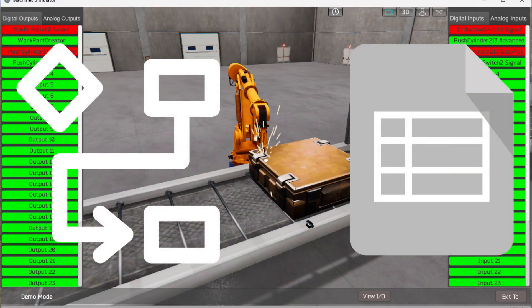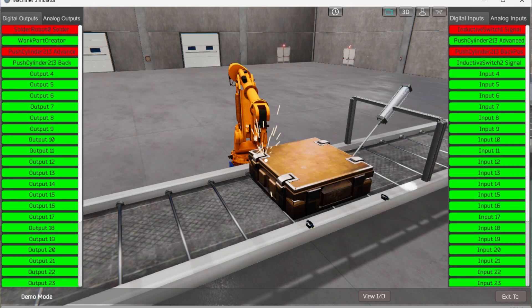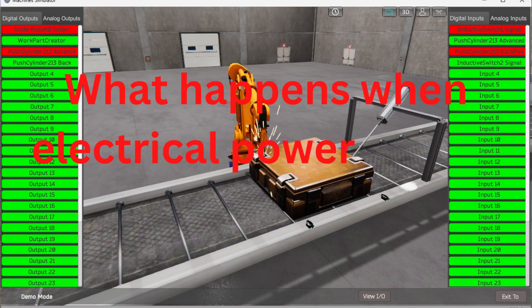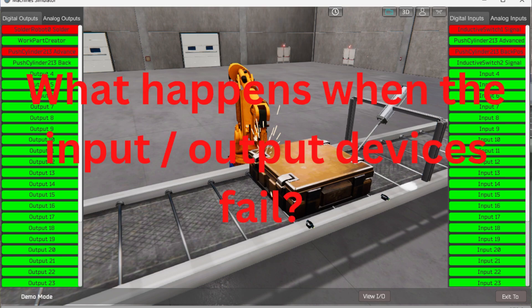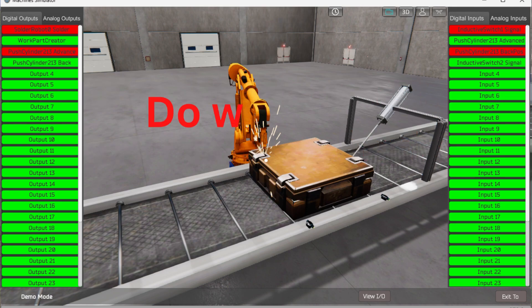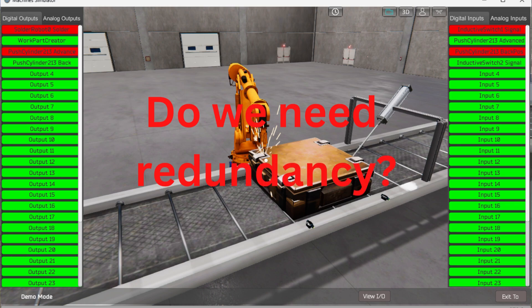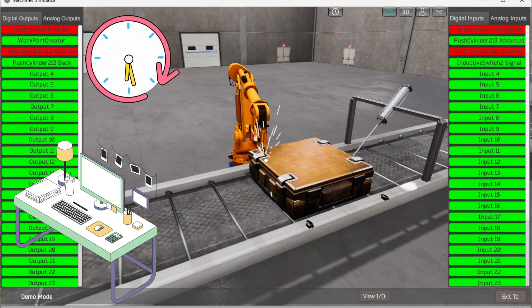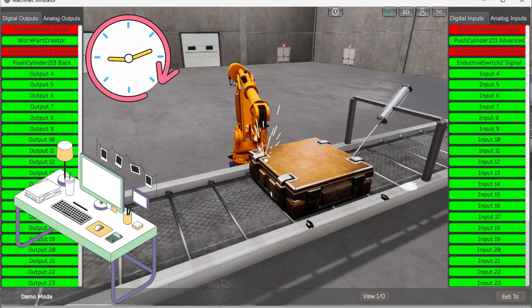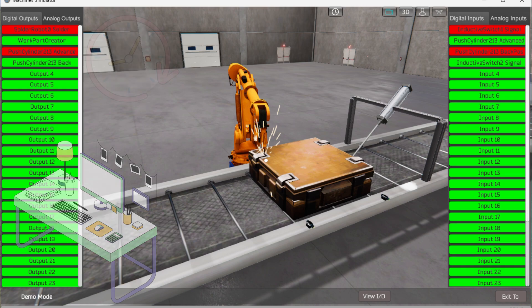A flowchart, sequence table, or detailed sequence description is used to fully understand the process that needs to be controlled. It must also answer questions like: what happens when electrical power or pneumatic air is lost? What happens when the input and output devices fail? Or do we need redundancy? This step is where you'll spend most of your time. Understanding everything about the operation will save you time and help prevent you from continuously rewriting the PLC program logic. Knowing all these answers up front is vital in the development of the PLC program.